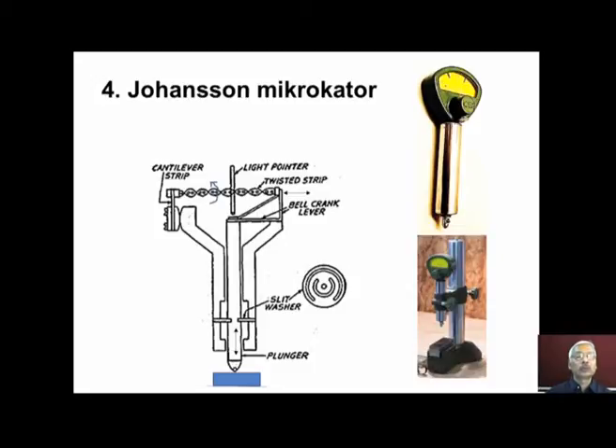We have the two S-shaped parts. These two parts are assembled by using this flexible slit washer. Now in the middle we have the plunger, which moves up and down depending upon the workpiece height, and then there is a bell crank lever. One end of the bell crank lever is connected to this S-shaped body, and the other end is connected to the top end of the plunger. And then there is a metallic twisted strip. So here we have a cantilever strip. Between the cantilever strip and the bell crank lever, we have this twisted strip, and then at the center we have a light pointer.